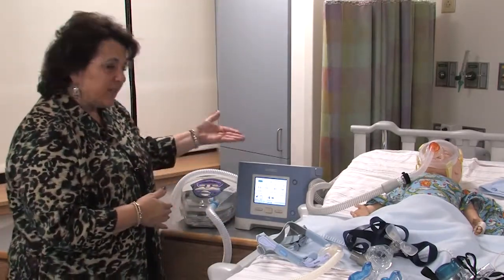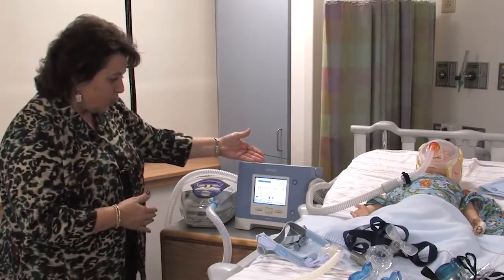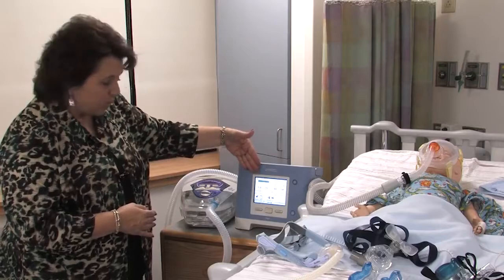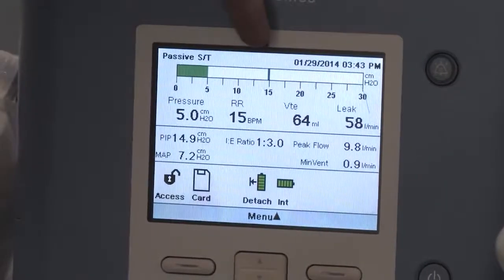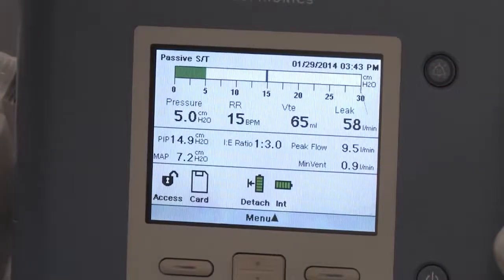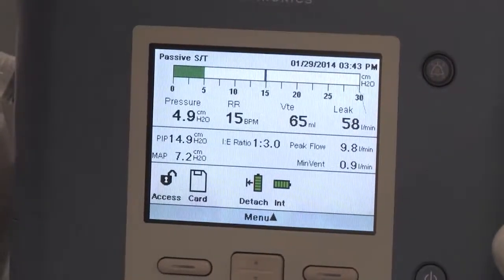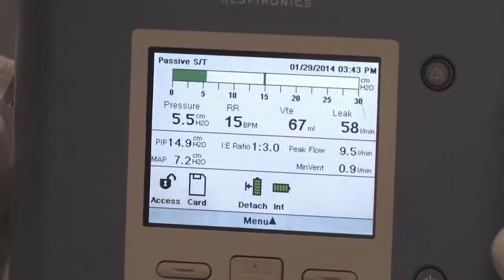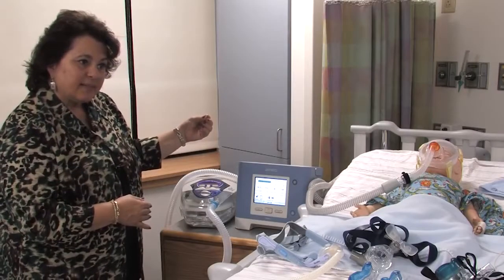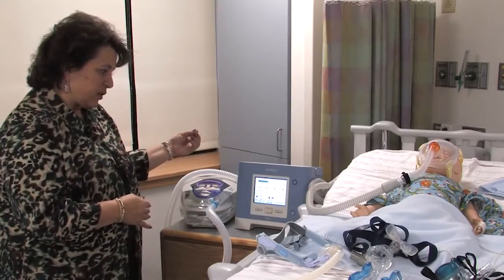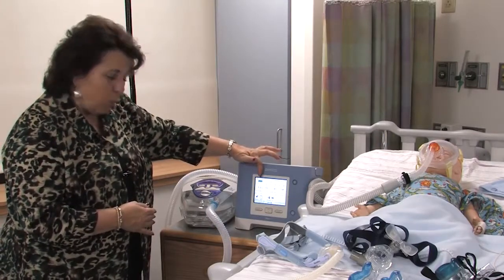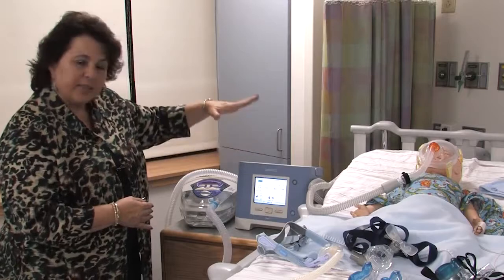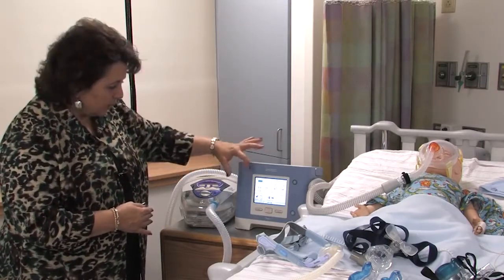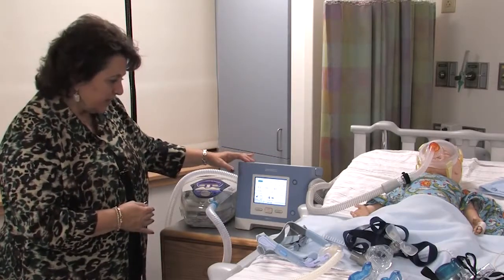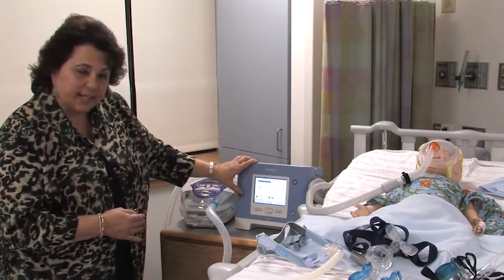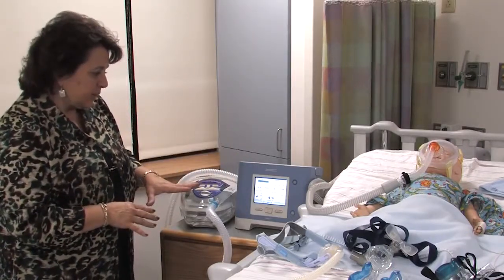So we're looking at these 2 devices here now. This is one that we're seeing on BiPAP support, and you can see that this child's getting pressure up to 15 and down to 5, up to 15 and down to 5. So I would call this IPAP of 15 and EPAP of 5. That's the inspiratory pressure and the expiratory pressure. If I just had one pressure here, like the 5, and the patient was breathing in and out on their own, that would be called CPAP, and it would say CPAP here on this device. This device is a little bit more sophisticated than the standard machines used out in the community.